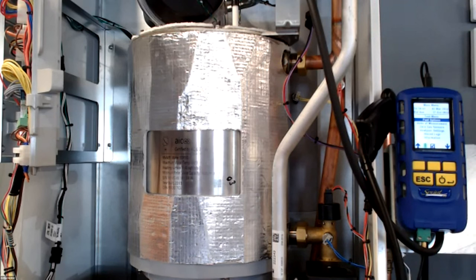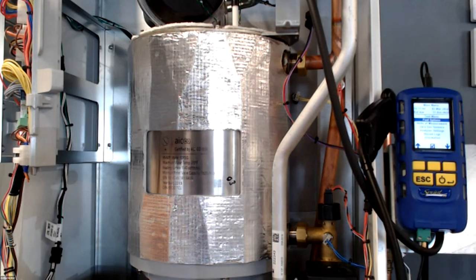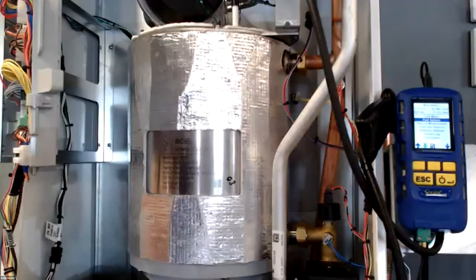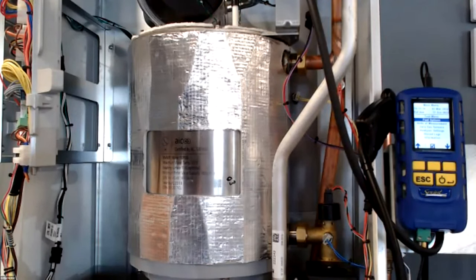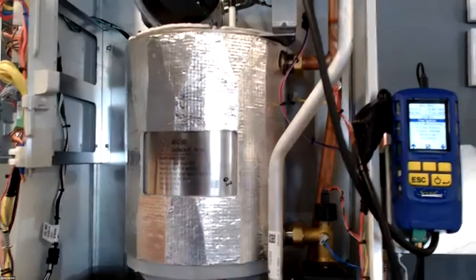There's issues on jobs. Then you're going to want to go ahead and oversize that gas line and go extra heavy with it to give yourself volume, because you don't have a pressure issue. You have a volume issue. You're dropping too much. So if you can give yourself at least 10 feet, that usually gives you enough and you can size that gas line accordingly. So hopefully that answers, but yeah, 2 inches is much too much of a drop. 1 inch is what we want to see. I mean, if it's 1 inch, maybe 1.5, but.